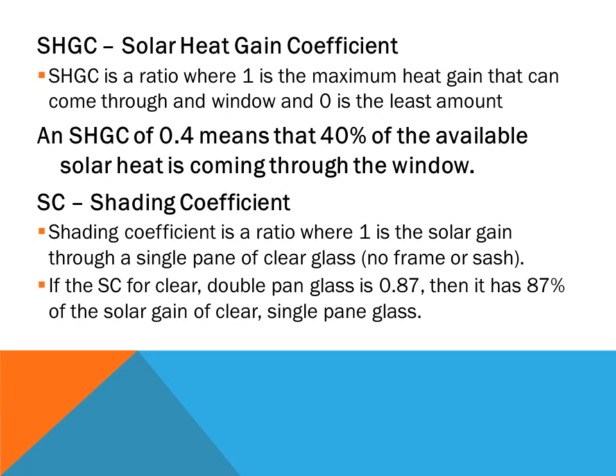Because of this, we look at something called the Solar Heat Gain Coefficient for windows, abbreviated as SHGC. It is a ratio where one is the maximum heat gain that can come through windows and zero is the least amount, and we look at this as percentages. For example, an SHGC of 0.4 means that 40% of the available solar heat is coming through the windows.